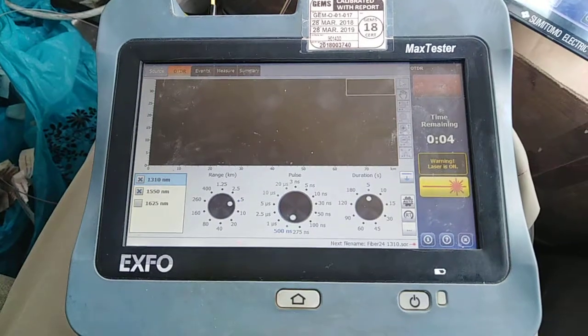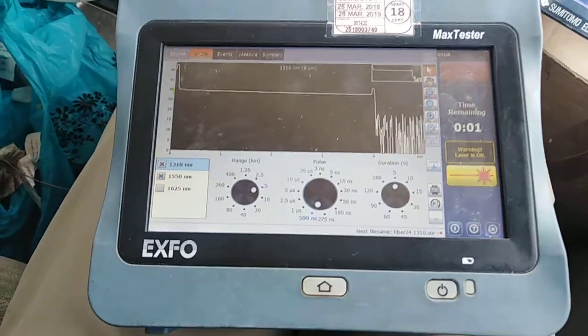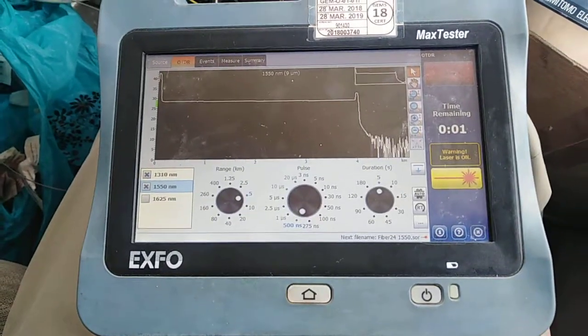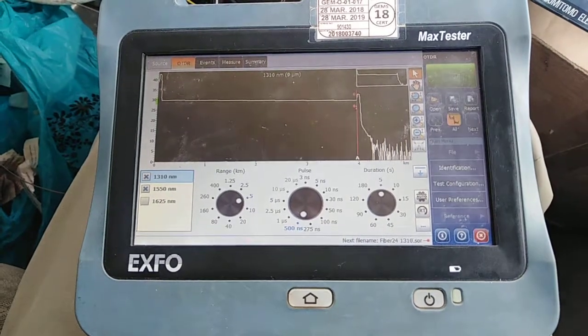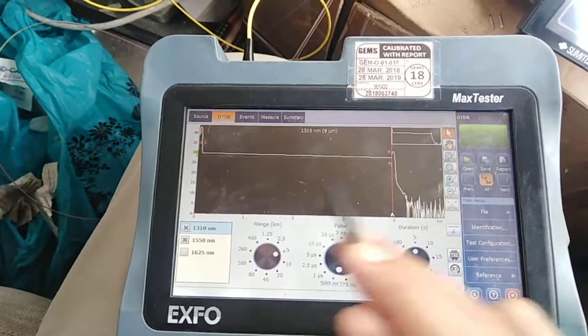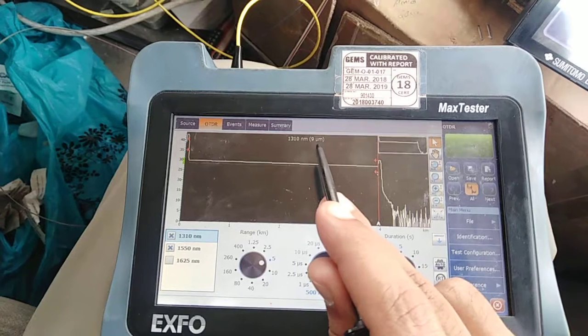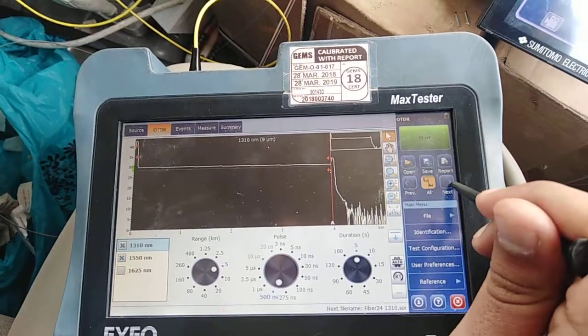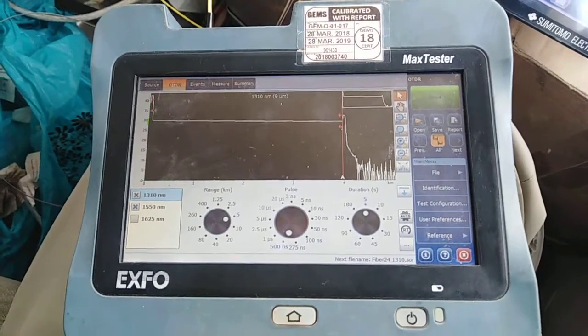I have selected a duration of 5 seconds for each wavelength — 1310 and 1550 nanometers. Analysis is in progress. The fiber has now been tested. You can see here: 1310 nanometer, 9 microns — this is the size of the core. You can go next for 1550 nanometers.